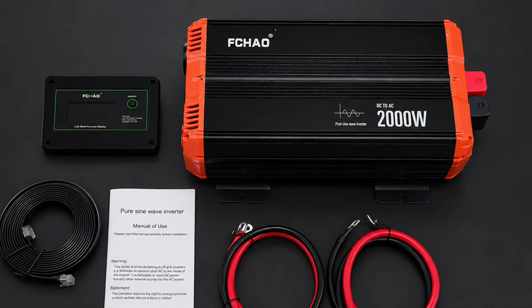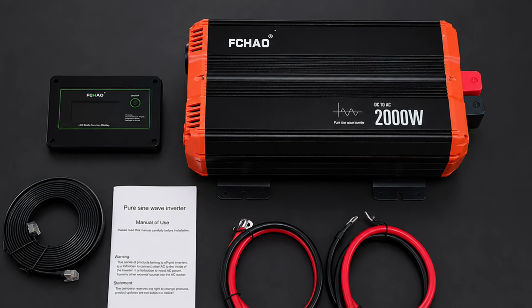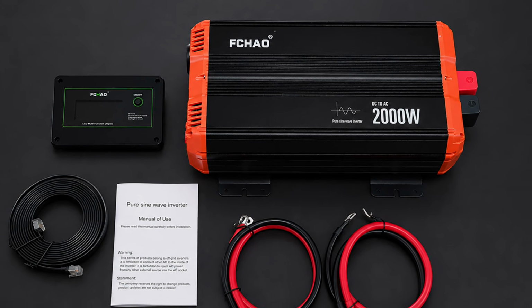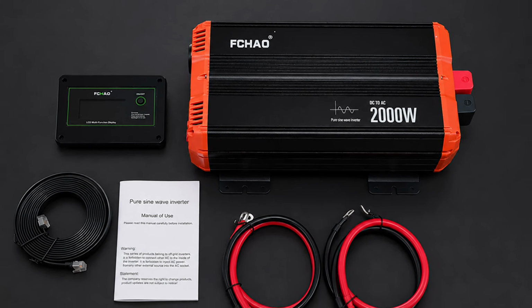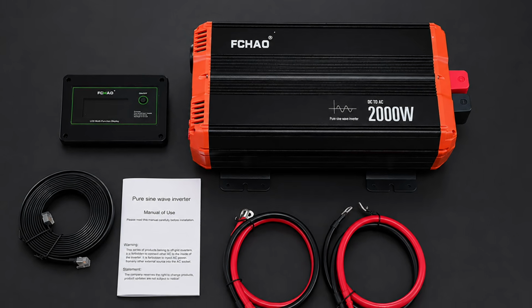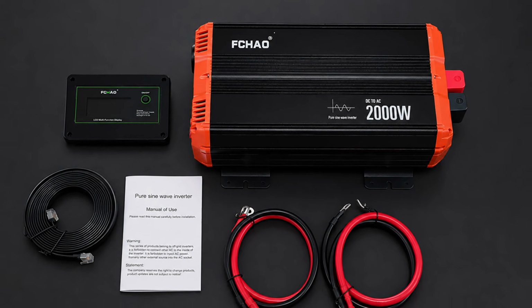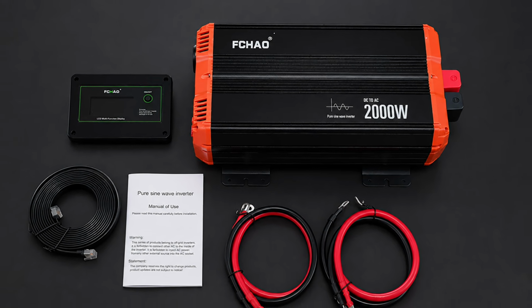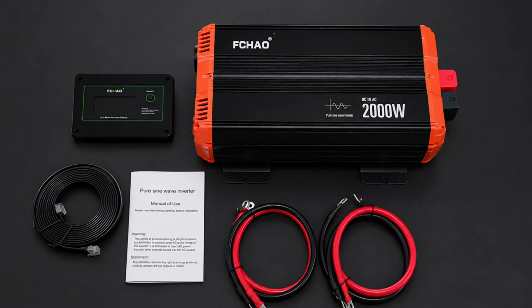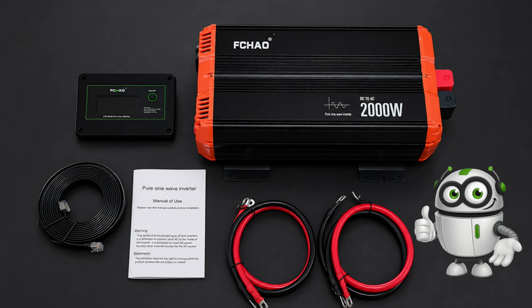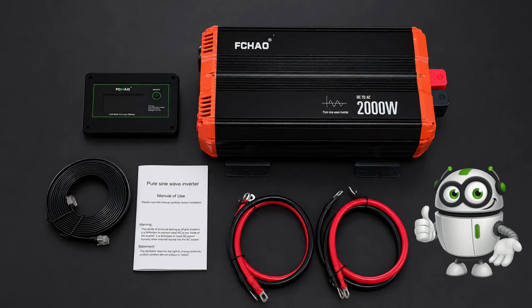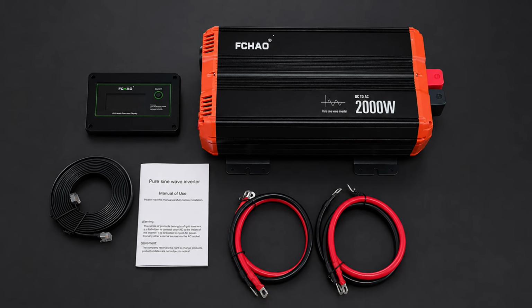The package includes the inverter itself, 2 pairs of power cables for connecting to the battery, a remote display, a cable for connecting it, and a small manual. The power cables here are not one thick pair, but 2 parallel pairs of equal length. They must be connected together. This way the current is distributed between the wires, and the cables themselves remain more flexible and easier to route.